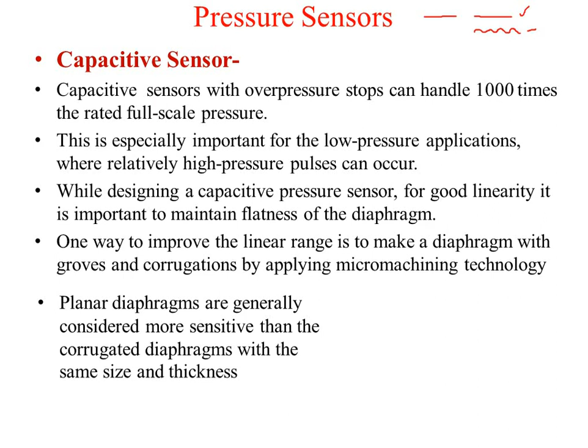Just like a tin. The elasticity of this type of diaphragm is very high, so you can improve its linear range, and this will give you a good linearity as compared to this one. The planar diaphragms are generally considered more sensitive than the corrugated diaphragms. So the sensitivity of the flat one is more as compared to the corrugated type of diaphragm.